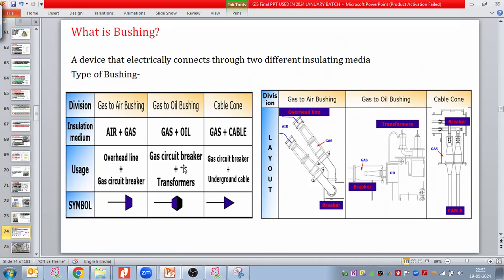So the gas to oil bushing is connecting the gas to the transformer. So we generally take this kind of symbol. For gas to cables, when we require gas to cables, we generally take this kind of arrow to indicate the terminations of equipment. So here we have gas to air, gas to oil. Now GIB directly terminating on the transformer bushings. And here we have gas to air, a cable. So the cable is coming and it is terminating to the cable chamber of the GIS.